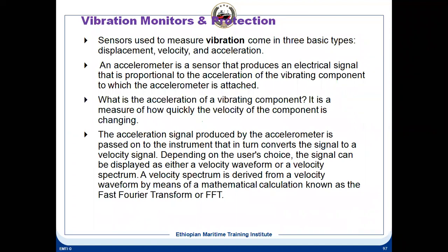Vibration monitors and protection. Most heavy duty motors, wherever you have compressors and so on, and heavy duty fans, use vibration monitors. The sensors used to measure vibration come in 3 types: displacement, velocity, and acceleration. An accelerometer is a sensor that produces an electric signal proportional to the acceleration of the vibrating equipment to which it is attached.